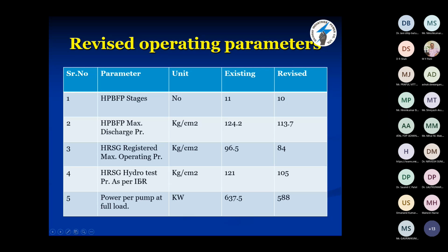Hydro test earlier we were giving at 96.5 into 1.25, that is 121 kg. After revision, we have to give the hydro test at 105 kg. And the pump power per pump at full load was 637.5 kilowatt. Now it is reduced to 588 kilowatt per pump.